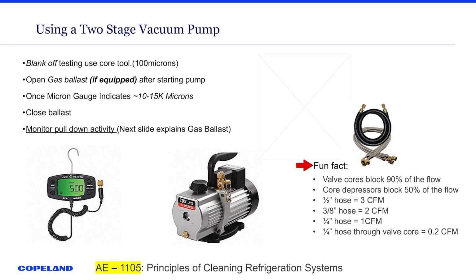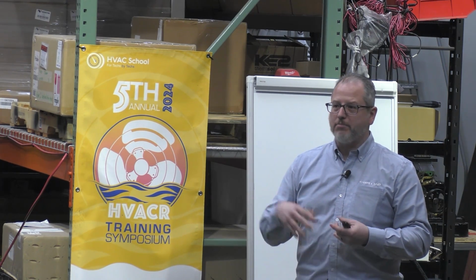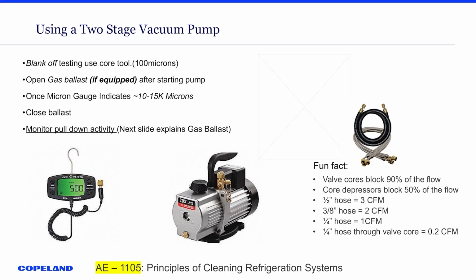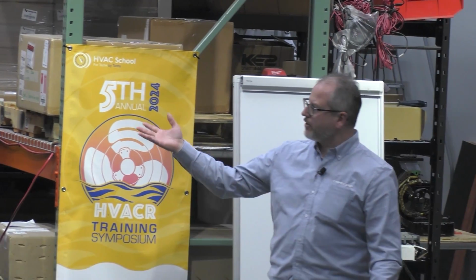I know for years when I used to evacuate systems, I always used my manifold gauge set just because that's how I was taught, right? And now that I've figured things out a little bit more as we learn, right? We're continually learning in our industry new ways of doing things better and saving time. Through that 1/4-inch hose with valve cores in there, even if I was using a 6 CFM vacuum pump, I was only getting 0.2 CFM through my hoses, right? So once you start pulling those valve cores out, putting bigger hoses on, you're going to be able to evacuate that system a lot quicker, right?